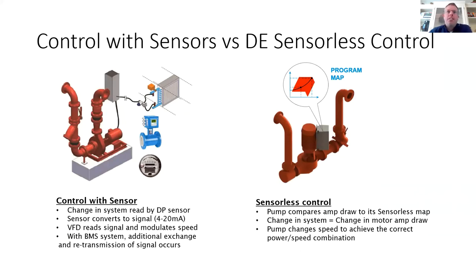So finally, in summation, traditional pump control schemes sense changes in the system via feedback from a differential pressure sensor located somewhere out in the system and modulates the VFD speed to maintain a certain differential pressure set point. BMS systems often incorporate separate water flow and power meters as additional data points for the plant operators.